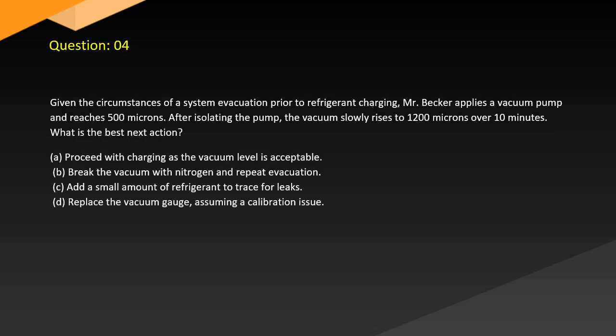Question 4. Given the circumstances of a system evacuation prior to refrigerant charging, Mr. Becker applies a vacuum pump and reaches 500 microns. After isolating the pump, the vacuum slowly rises to 1200 microns over 10 minutes. What is the best next action?